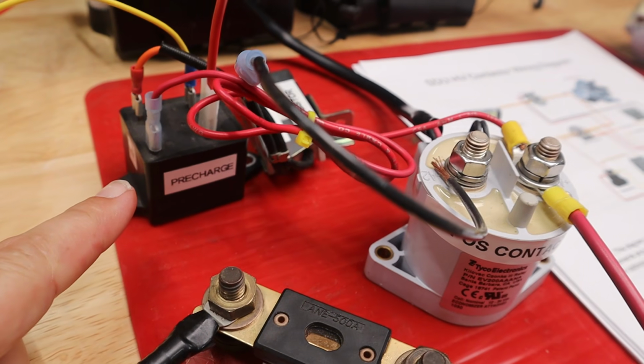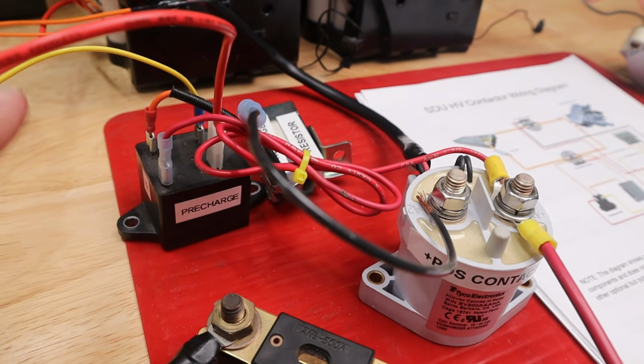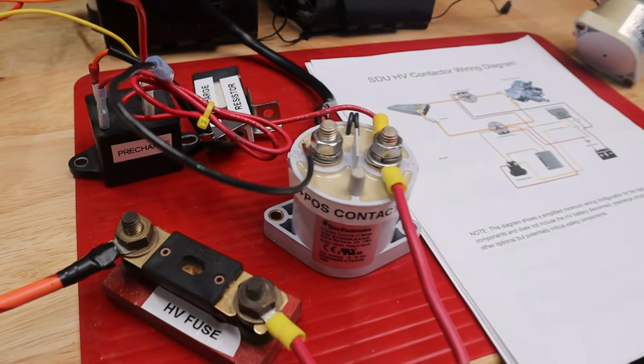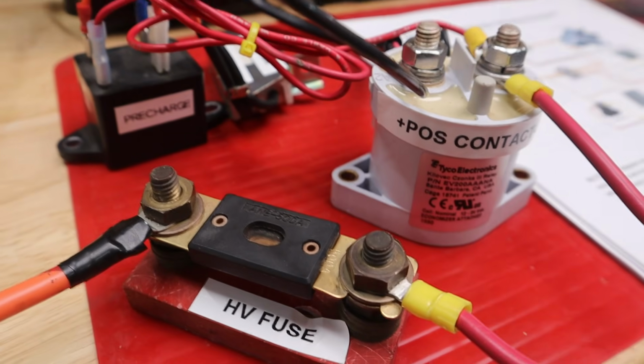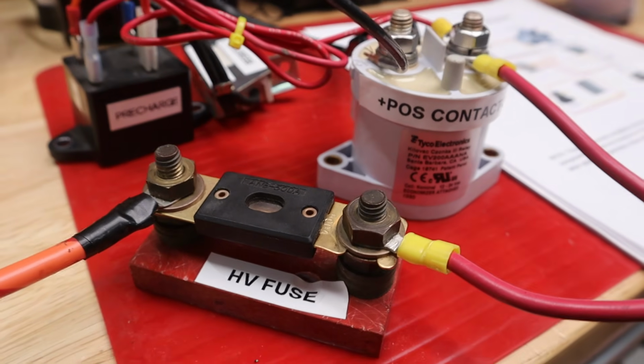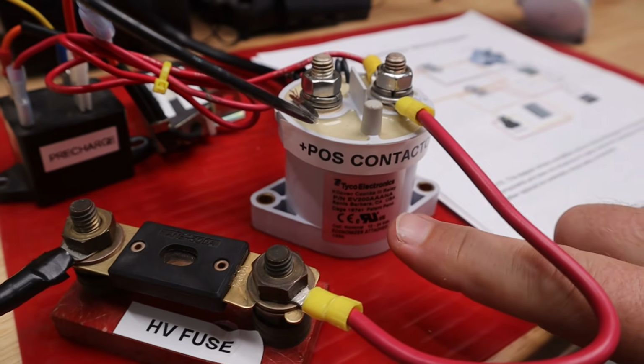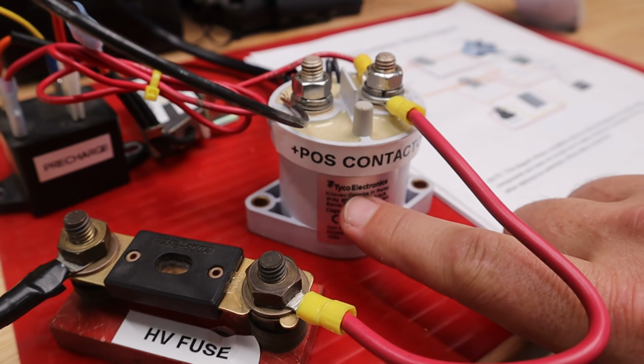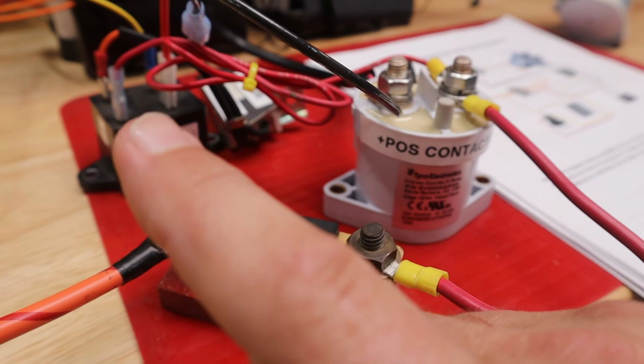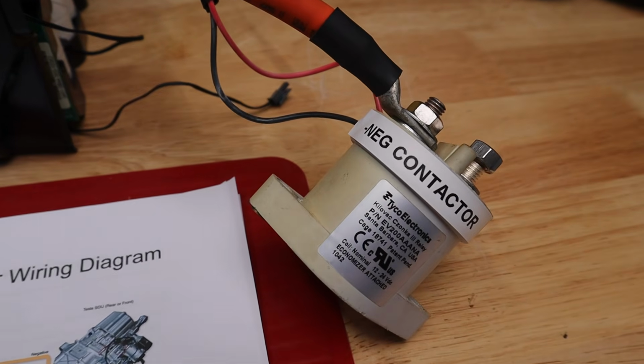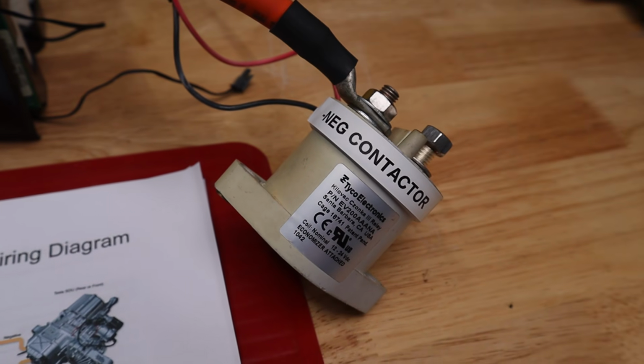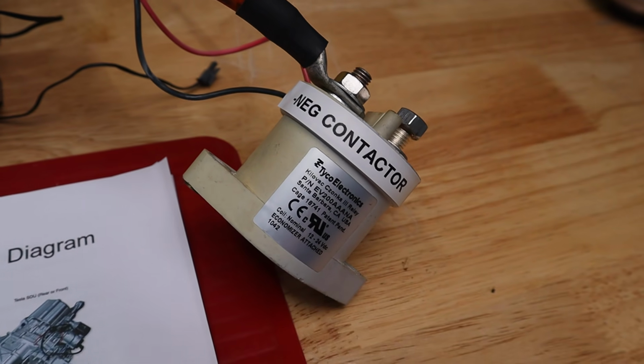One of those is the pre-charge. So right away we'll get some power going through that pre-charge resistor, pre-charging everything up. Then it's the logic board and the programming on it that will say when to turn the positive contactor on and the pre-charge back off. But also right at this moment, the negative contactor is just switched on and off with the key switch.